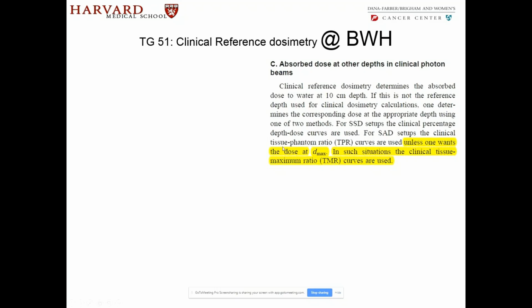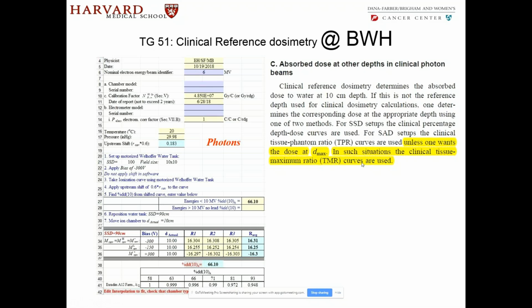We calibrate the machine at Dmax. That is why in such situations, the clinical tissue maximum ratio, the TMR curves, is what we use to calibrate it. I'm going to send you this as part of the notes. This part describes the full procedure of the measurement: set up the tank, apply bias, take the ionization curve using the tank, apply the upstream shift. The upstream shift for our chambers is 0.6 times the cavity value. If the cavity value changes based on the ion chamber, you will have to choose your own.